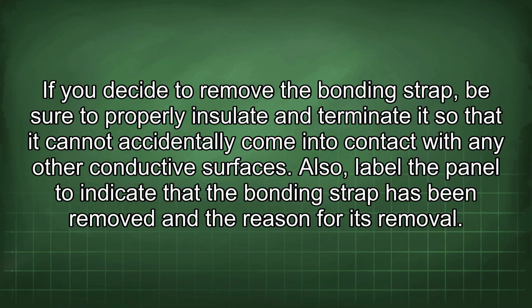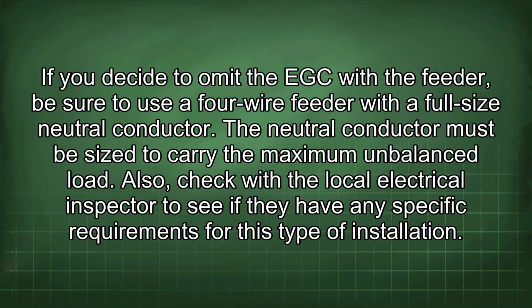If you decide to remove the bonding strap, be sure to properly insulate and terminate it so that it cannot accidentally come into contact with any other conductive surfaces. Also, label the panel to indicate that the bonding strap has been removed and the reason for its removal. If you decide to omit the EGC with the feeder, be sure to use a 4-wire feeder with a full-size neutral conductor. The neutral conductor must be sized to carry the maximum unbalanced load. Also, check with the local electrical inspector to see if they have any specific requirements for this type of installation.